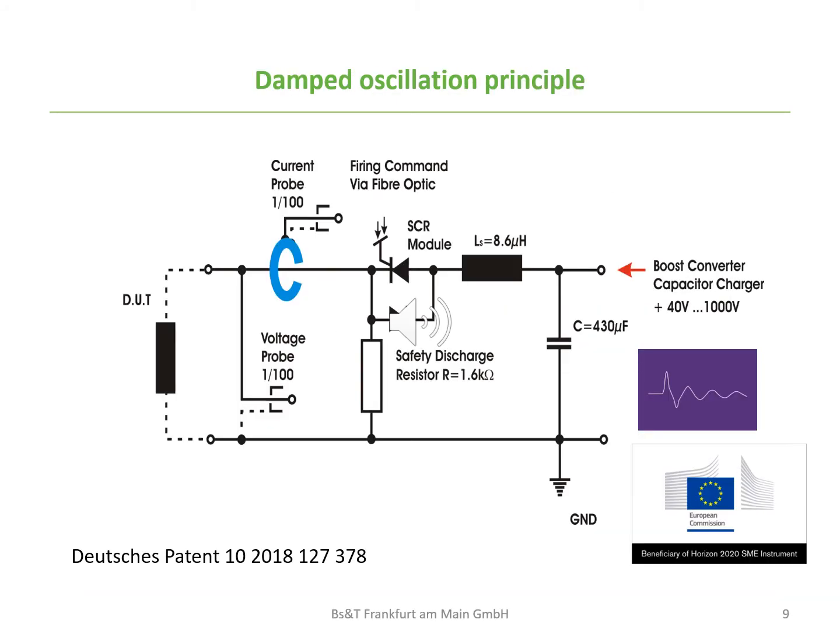The physical principle is a damped oscillation process. A thyristor is triggered by the control unit, and it generates a fully reversible current. A nonlinear device under test with a non-storage capacitor forms an LC resonance. The resonance is sampled with voltage and current decay. Through the voltage decay, we evaluate a Q factor or insertion losses. And through the di/dt method, the differential inductance can be data processed.